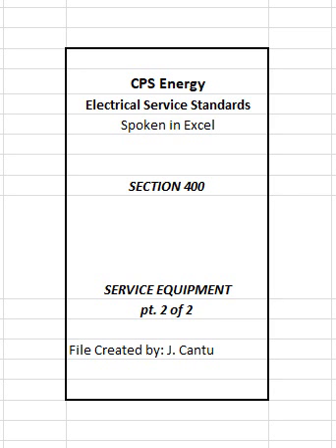Exception. Disconnecting means installed as part of listed equipment and used solely for the following shall not be considered a service disconnecting means: 1. Power monitoring equipment, 2. Surge protective device, 3. Control circuit of the ground fault protection system, 4. Power operable service disconnecting means. 407 Grouping of disconnects. The multiple disconnects permitted by the NEC and Article 405, up to 6, shall be grouped. Each disconnect shall be marked to indicate the load served.